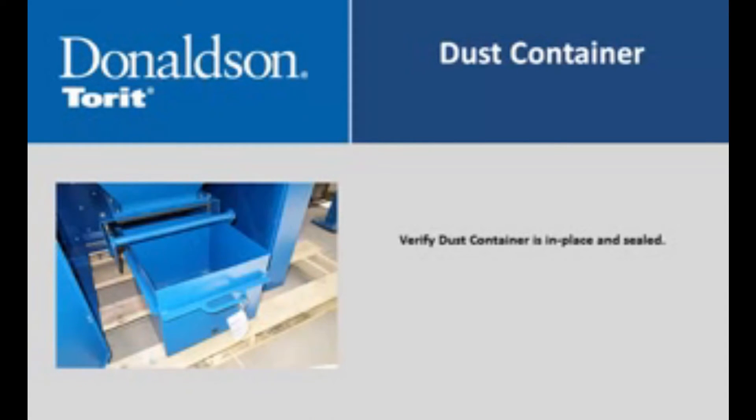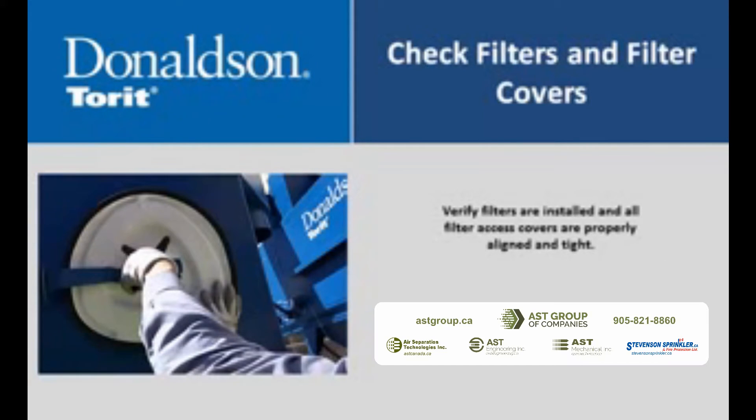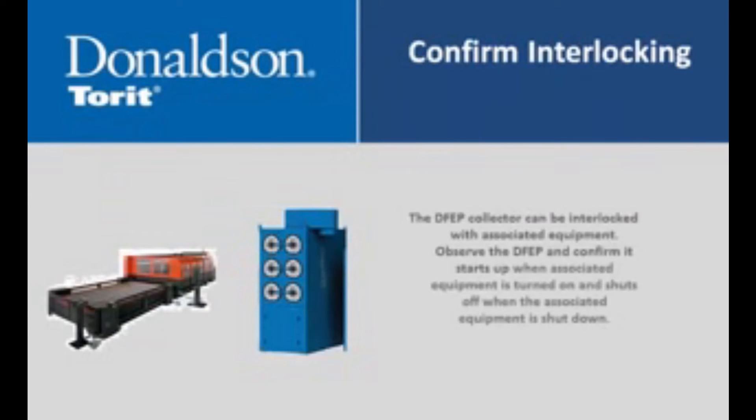Verify the dust container is in place and properly sealed. Verify that all cartridge filters are installed and all filter access covers are properly aligned and tight. Start the fan and verify design air volume. Adjust the airflow control damper to limit airflow to design volume as necessary. The DFEP collector can be interlocked with associated equipment. Observe the DFEP and confirm it starts up when associated equipment is turned on and shuts off when the associated equipment is shut down.